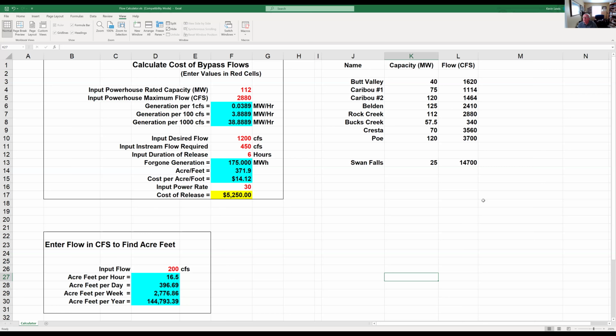In this case I inputted 1,200 CFS, and what I subtracted was a minimum in-stream flow that was already required, so it shouldn't count toward this recreational flow, that's the 450 CFS. I used a duration of 6 hours. It tells you the foregone generation in megawatt hours, how many acre-feet that is, the cost per acre-foot, and the cost of the release. So a 1,200 CFS release minus the 450 CFS in-stream flow for 6 hours at $30 a megawatt hour would cost $5,250, what it costs the utility to not generate and instead release water for recreation.